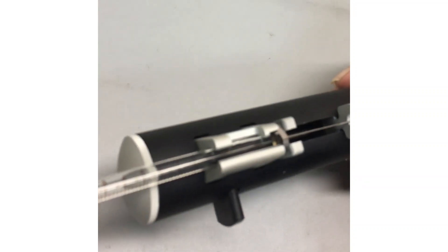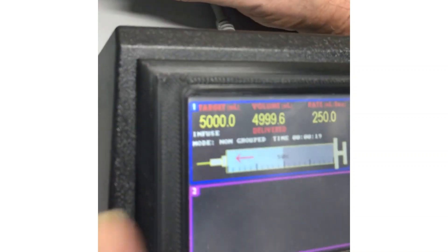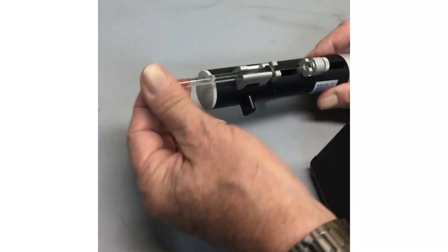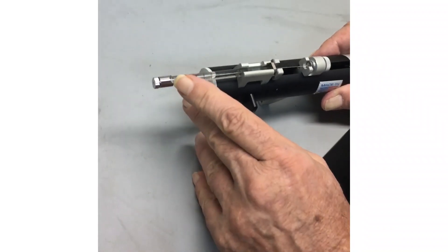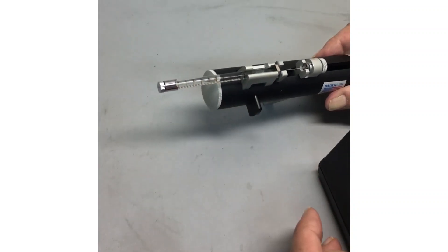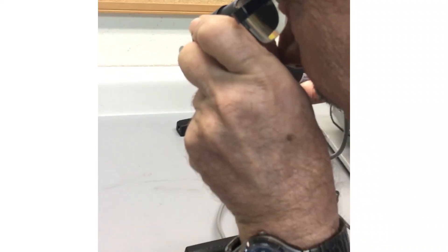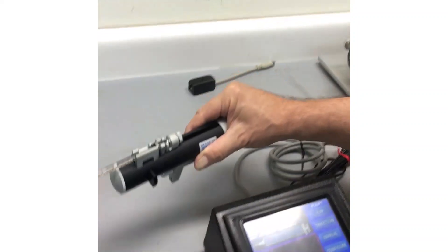So if I run this again — because we set it up at 5,000 — it's going to end up at the zero mark that you can just see through this little cutout in the ferrule at the end of this syringe. What you won't hear is the motor binding as it tries to drive the plunger below the zero mark. If that does engage, you're going to hear a slight noise. And if I look in here — yep, that's right at the zero mark exactly.